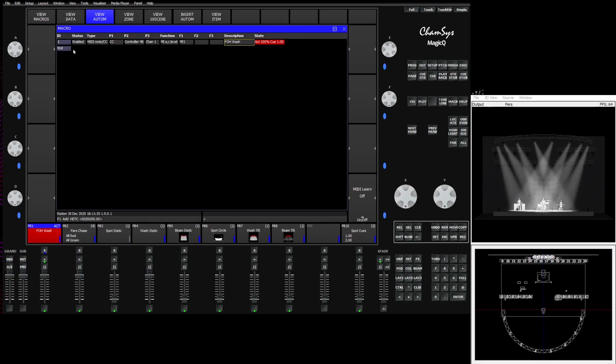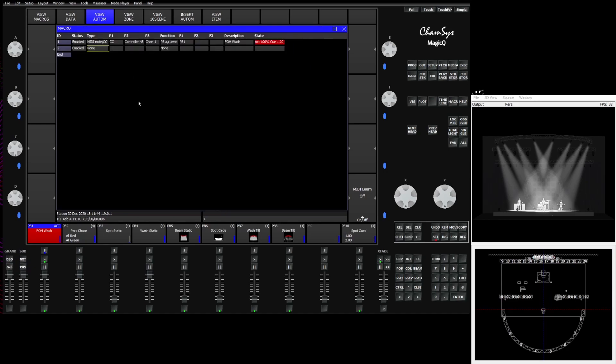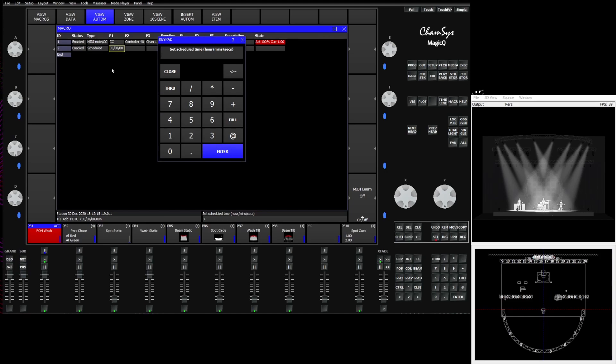The action is similar for any other automations you may want to add. So if we insert another automation, this time we're going to choose something as simple as a scheduled event. P1, P2, P3, parameter 1, 2, and 3 will only be used in some of the types that you choose. For instance in schedule we can set the time and the date using P1 and P2. Refer to the manual for a little bit more information on how to input that. But if I wanted something to fire at 11 o'clock every day, you see it says get set scheduled time, hours, minutes, and seconds. I can say at 11 o'clock and 0 seconds every day.